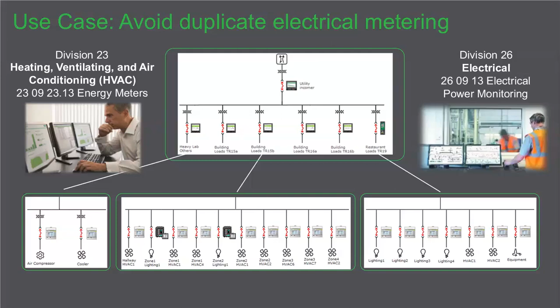This is showing an intelligent breaker system, an intelligent management system that's more factory installed, connecting nowadays with a communication bus directly to the BMS. A lot of times that happens, but often it's just on the mains coming in and not the subsystems underneath for sub-metering. A lot of that can be done at the gear now instead of having to go and put in duplicate meters.